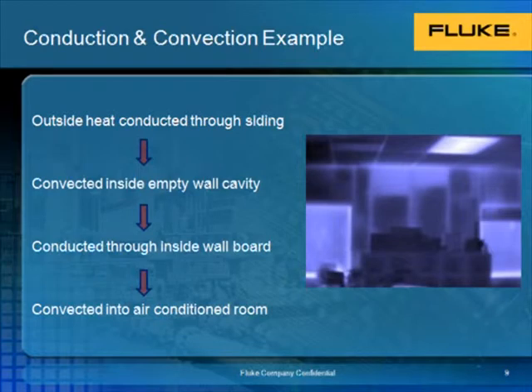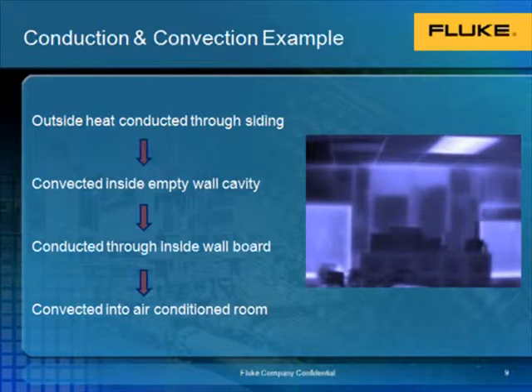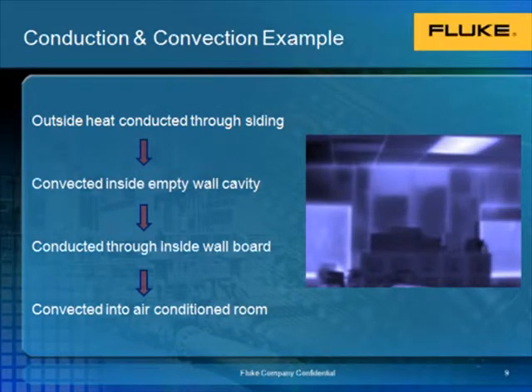In this slide, we see an example of where both conduction and convection are at work. We're looking from the inside of an air-conditioned room. Outside, there is heat being conducted through the siding. Next, it is convected through the empty inside wall cavity where insulation should be. From there, it is once again conducted through the inside wall board and then convected into the air-conditioned room. Be mindful that oftentimes more than one mode of heat transfer can come into play.